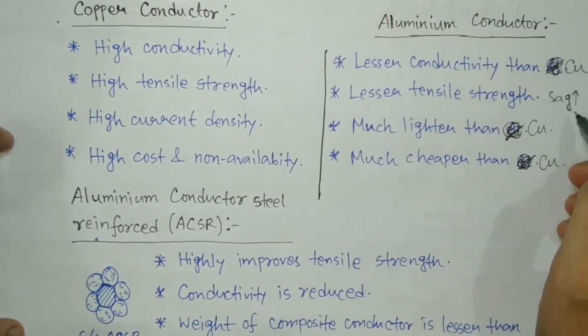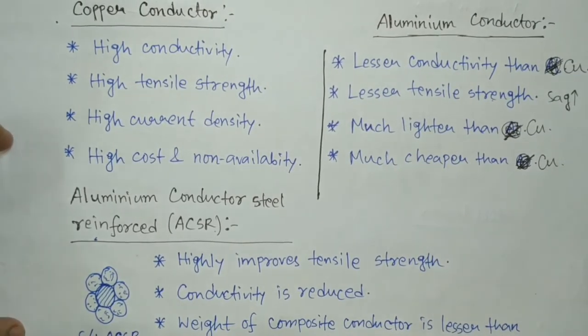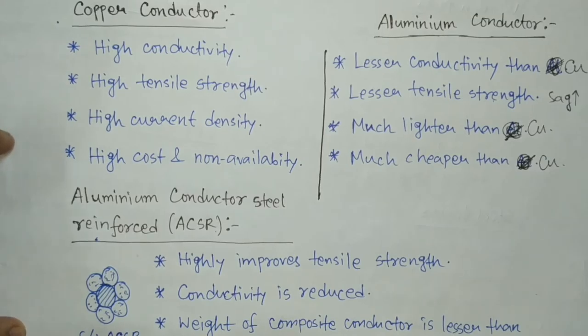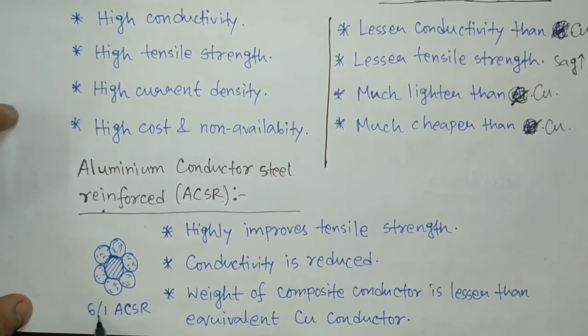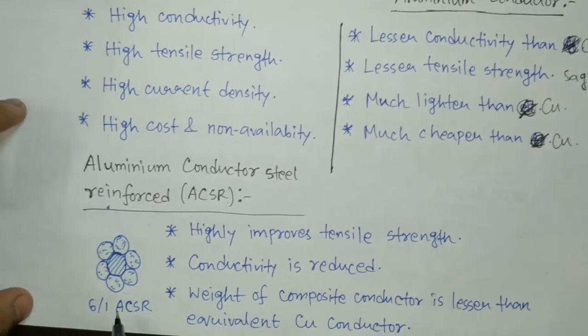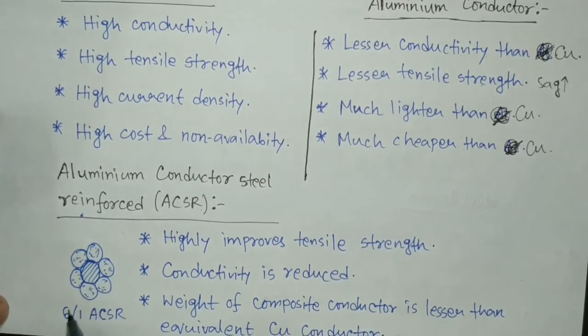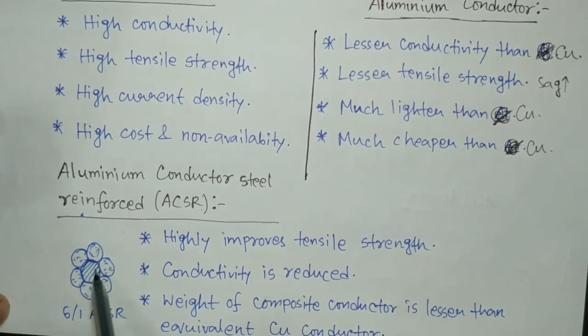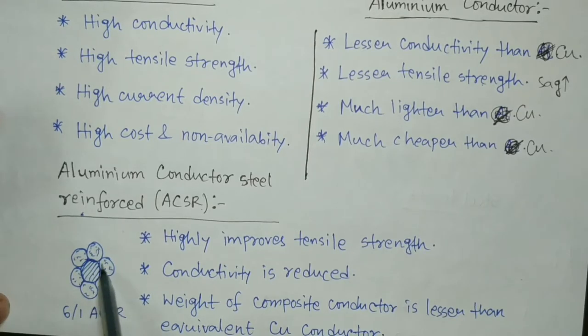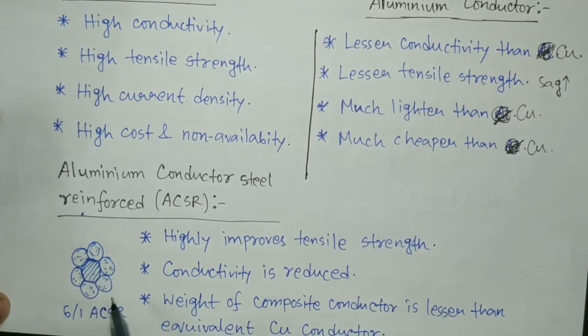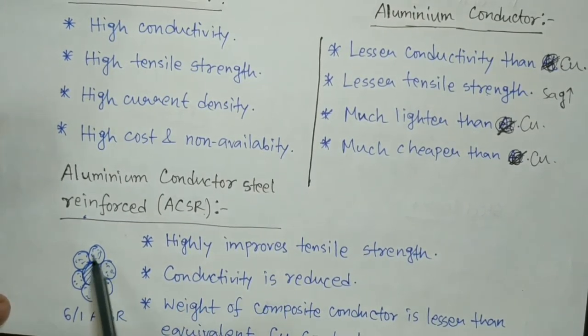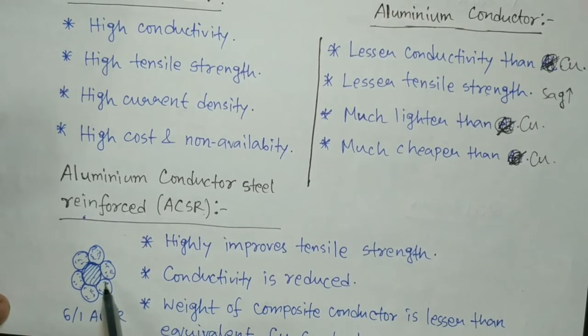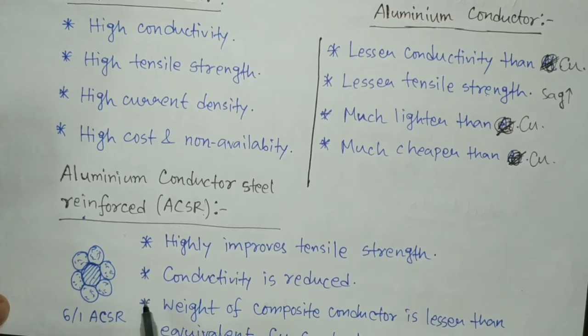This conductor looks like this — it is called a 6×1 ACSR conductor. It means there are 6 aluminium conductors and one steel conductor at the center. The 6 aluminium conductors surround the steel conductor which is right at the center. This structure gives very good tensile strength.